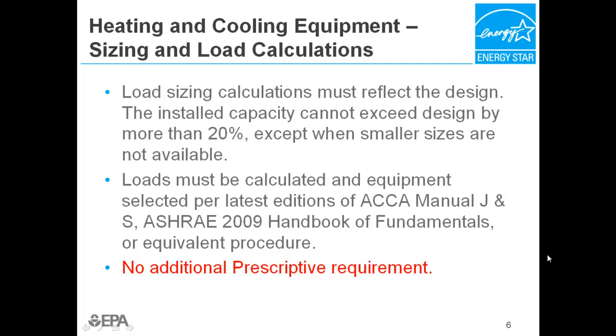The heating and cooling sizing and load calculation requirement is the same in both paths. Load sizing calculations must reflect the design. The installed capacity cannot exceed design by more than 20%, except when smaller sizes are not available. Loads must be calculated and equipment selected per latest editions of ACCA Manual J and S, ASHRAE 2009 Handbook of Fundamentals, or an equivalent procedure, and must use appropriate temperatures. As reviewed in the Performance Path webinar, indoor temperatures must be 70 degrees Fahrenheit for heating and 75 degrees Fahrenheit for cooling, and outdoor temperatures must be the 1% and 99% design temperatures. This prerequisite is the same in both Prescriptive and Performance Path.